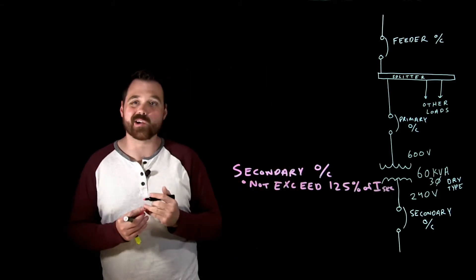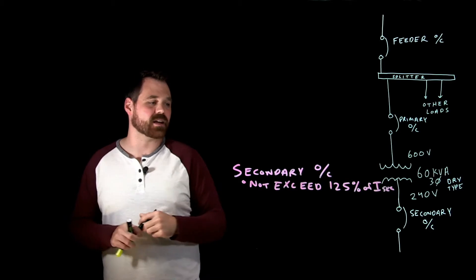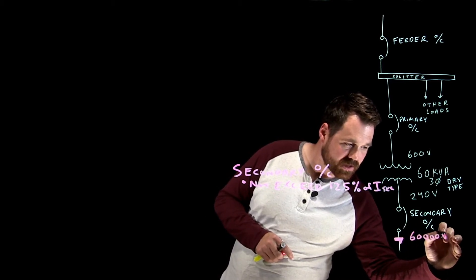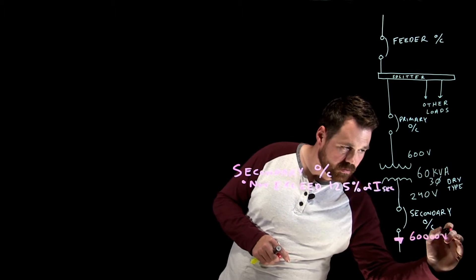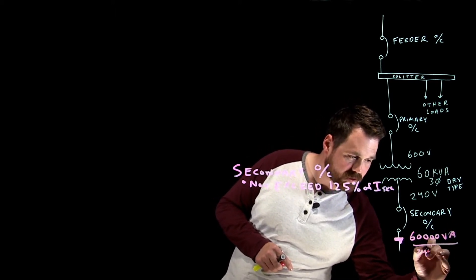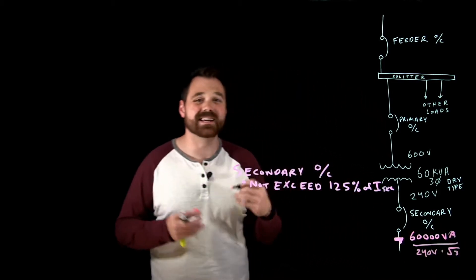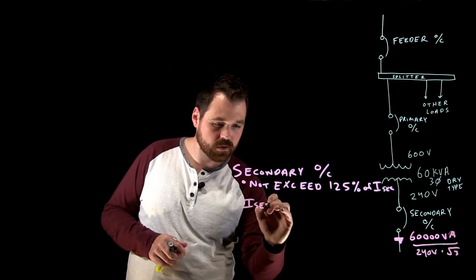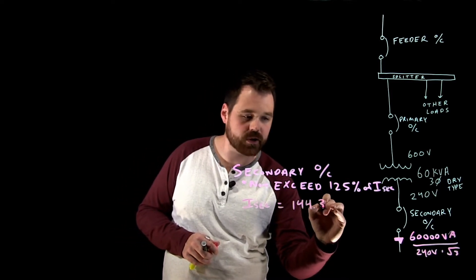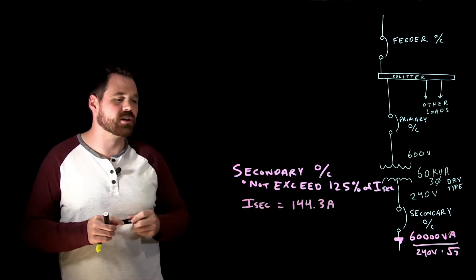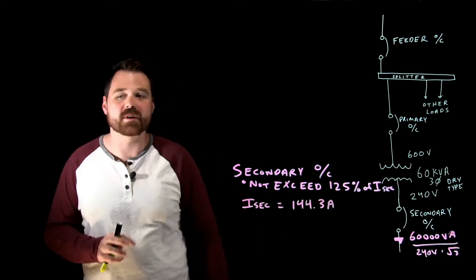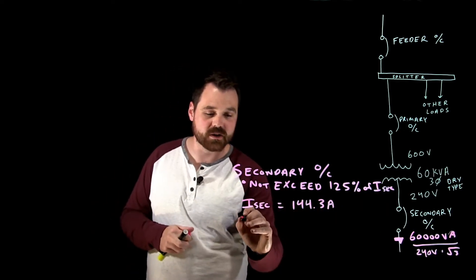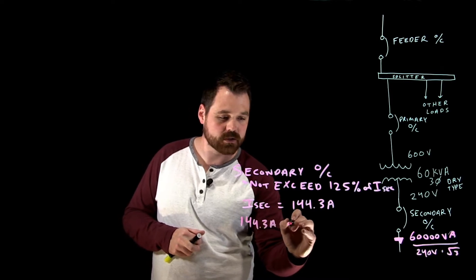In this case we're going to calculate our rated secondary current. I'm going to take my 60 kVA, 60,000 VA, divided by 240 volts times root three because it is a three-phase system. What I end up with is I secondary of 144.3 amps. Now I have up to 144.3 amps flowing on my secondary. My rule says that you can size that overcurrent device based on 125 percent so I'm going to go 144.3 amps times 125 percent which gives me 180.4 amps.